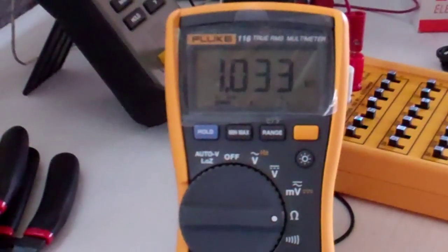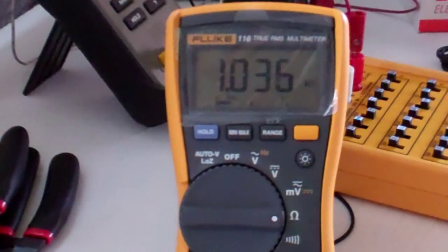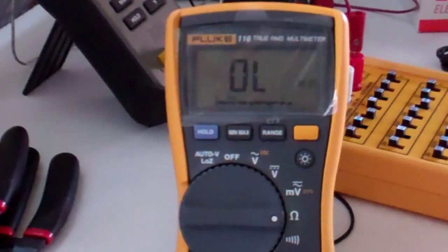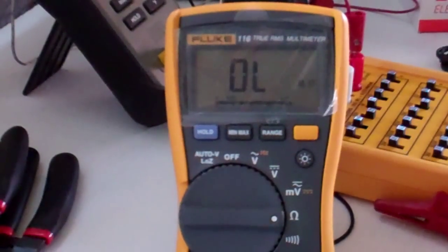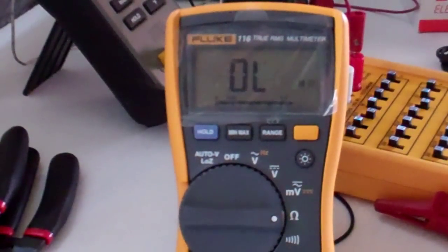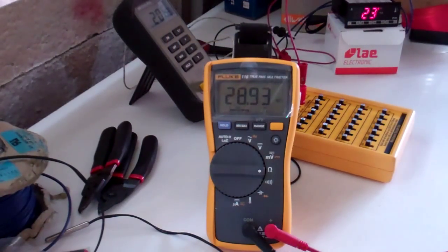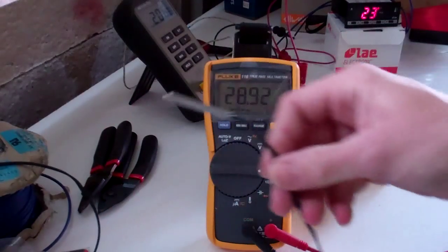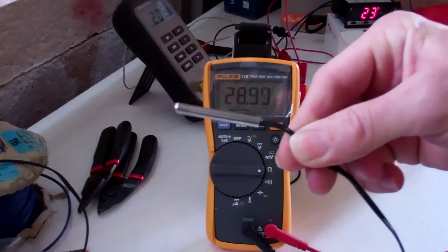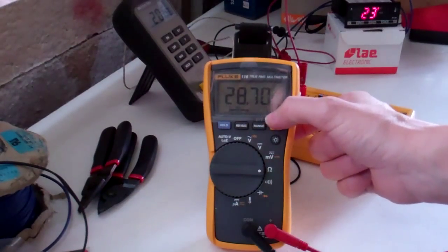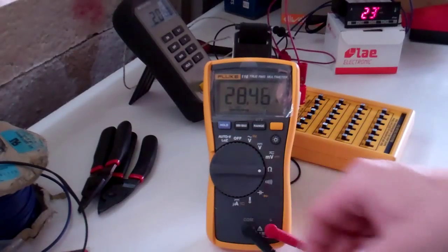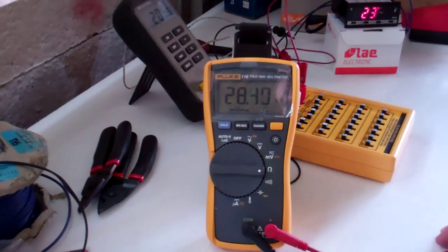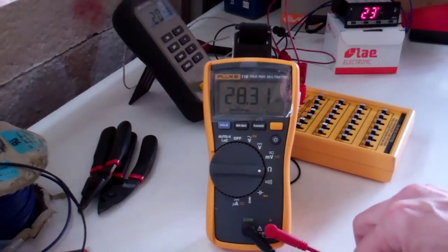So that's a PTC probe. Yeah, it's got another probe on there. That's a sort of a milk tank. Slightly faulty but you can see that's reading 28 kohms which is way over what the other two were reading. So again that's an even different style of probe.